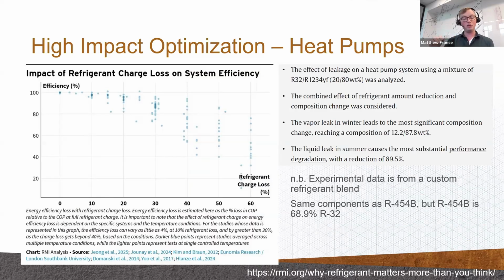So a lot of our current heat pumps use mixed refrigerants. So R410A is a blend, R454B is a blend. This particular study uses a non-commercially available blend, but it's the same component parts. So I think it's comparable. And what they're looking at here is as you lose more and more refrigerant, your system efficiency drops, and it falls off pretty fast, starting at about 20% loss.